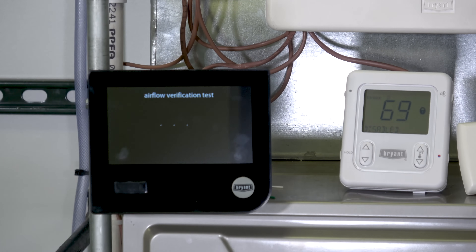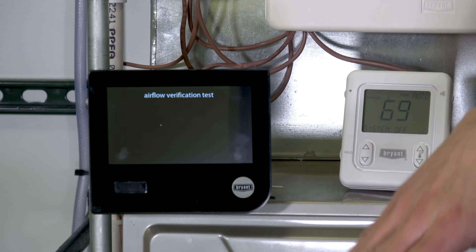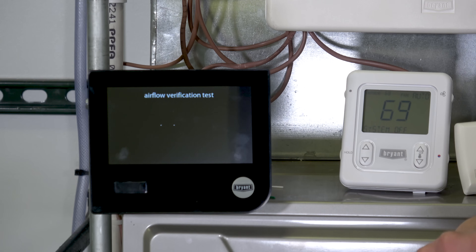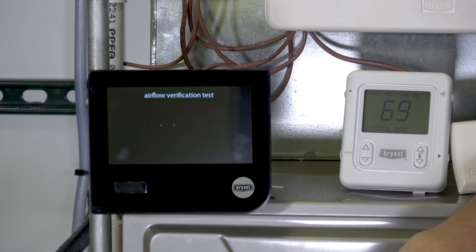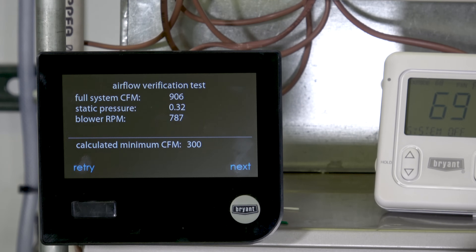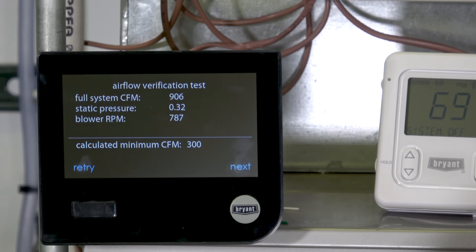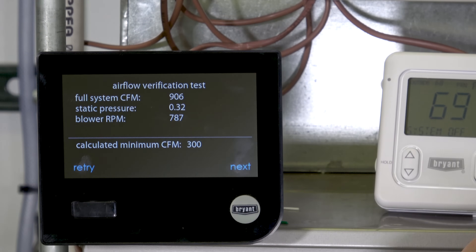Now it's going to do an airflow verification test — the exact same test as on a normal non-zoned Evolution/Infinity or Ion system, except it does the test first with all the dampers wide open. You can hear that ticking noise — that's the little motor opening up to make sure everybody's wide open. Our furnace ramps up and does the airflow test. The test is now complete: 906 CFM at 0.32 inches of static, blower RPM of 787.